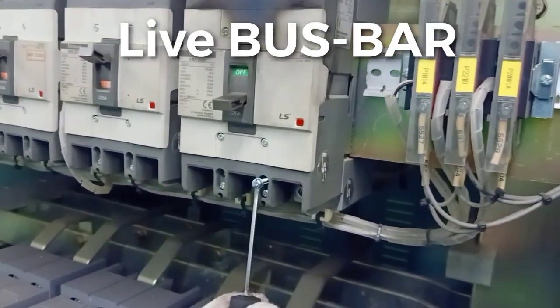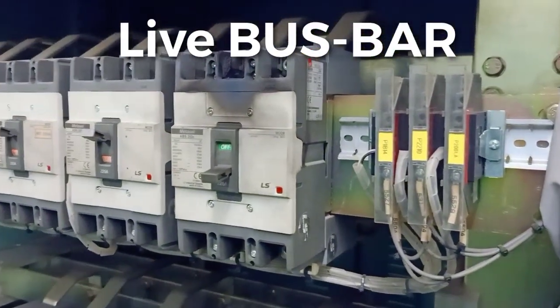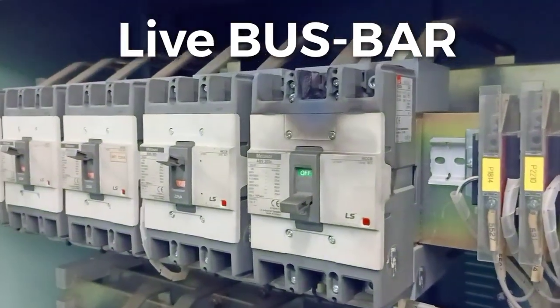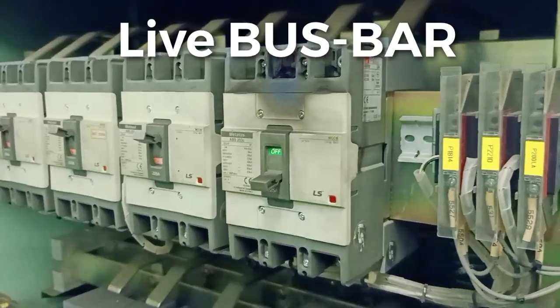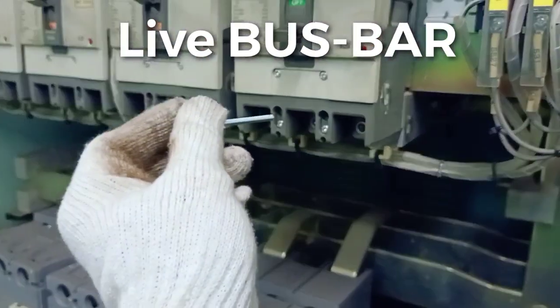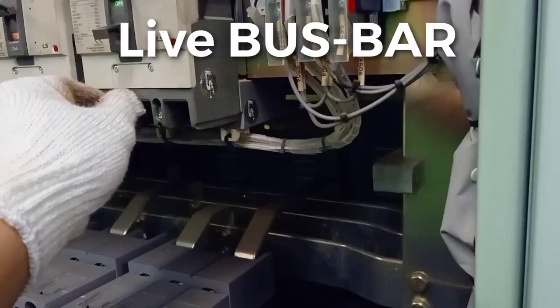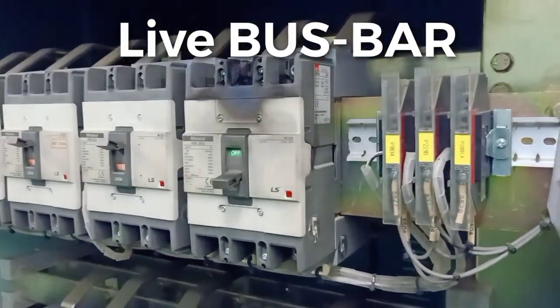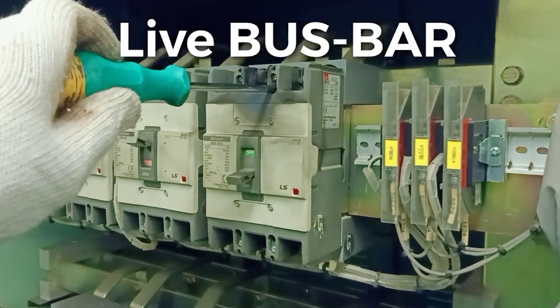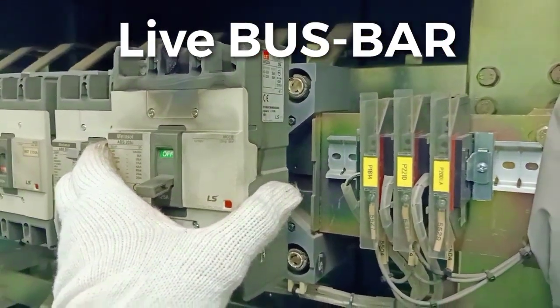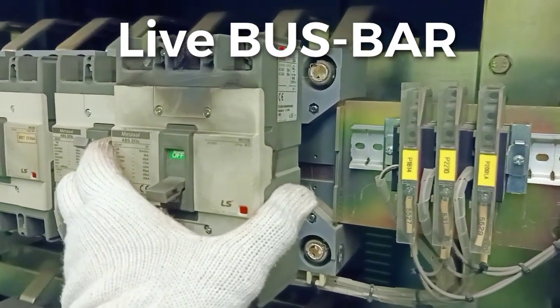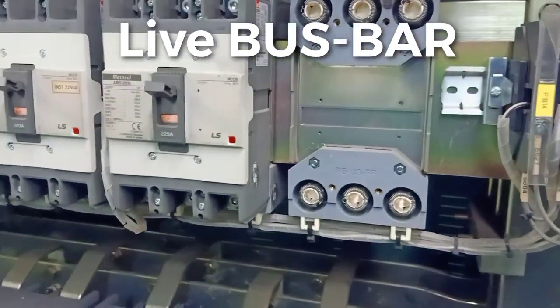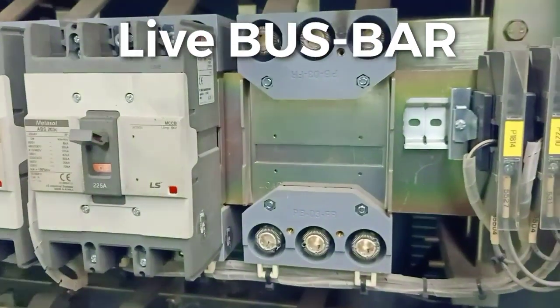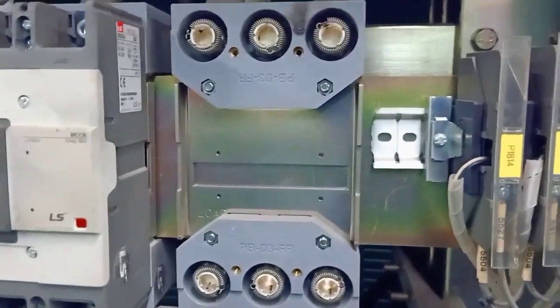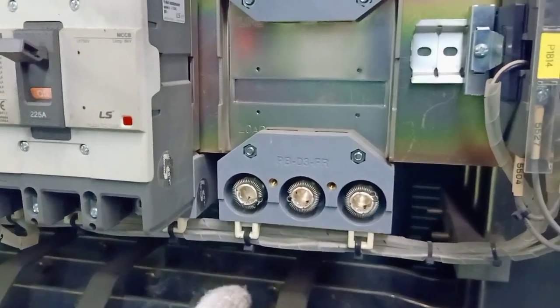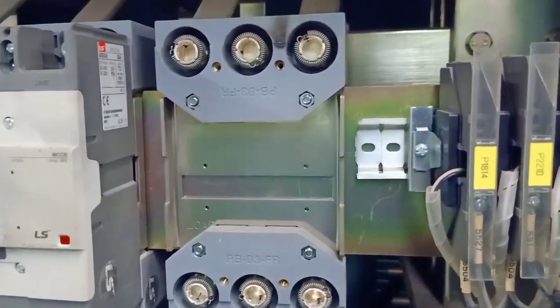First, remove this one screw. Next, the other one screw. Remaining one screw from the upper side, and one screw from the lower side. The last screw. This is it, removed already. Be careful, it's a live circuit. This line is going to the bus bar. So that's the base. Bus bar, and this is going to the load side, ballast pump number 2.